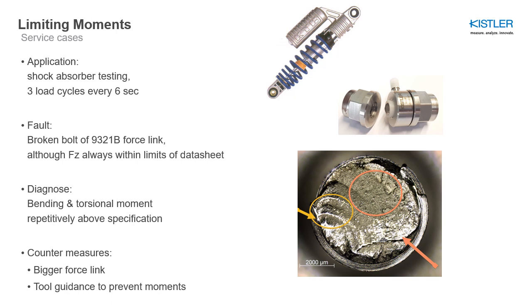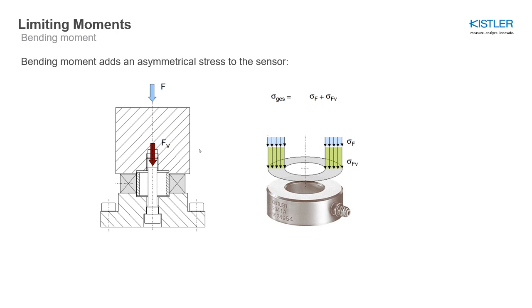Now, the diagnosis of this fault was that the bending and torsional moment was repetitively above specification. There are certain countermeasures, of course, to take. You can take a bigger force link, which is more rigid towards bending moments, or you control the movement of the shock absorber and build a tool guidance and prevent moments as such. Now, what's the problem of this bending moment? The bending moment adds an asymmetrical stress to the sensor, which is unfortunately not visible at all at the output of the sensor. So you can see here a normal force ring, which is built into a structure with a pretension bolt and a pretension force that you can see here in dark red, and you have a force that is applied by the process here in blue.